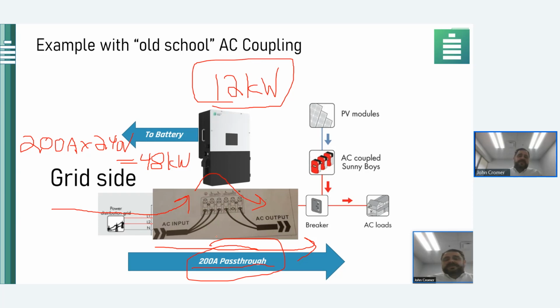In many jurisdictions, they'll say, well, you have to prove to me that the home doesn't go above 12 kW of power. Otherwise, you have to implement some kind of monitored load control to supply that power. In other instances, it may be a little bit more simple. It may just mean that when the customer goes into a blackout mode and then they use too much power, the inverter will turn off, and then the customer will have to realize that they can't run their air conditioning at the same time that they're doing their laundry and dishwashing, that they have to manage their energy through automatic means or manual means, one way or the other. And of course, later on in the program, we're going to talk about how to get even more power out of these systems.